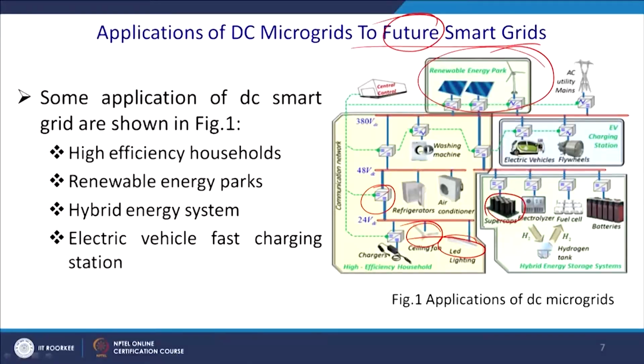To minimize the transient response or power mismatch over minutes, the system is supported because if you suddenly throw in an extra load, the bus voltage will sag, and the battery bank cannot take that amount of extra transient power instantaneously, so the extra power has to be channelized into the ultra capacitor.